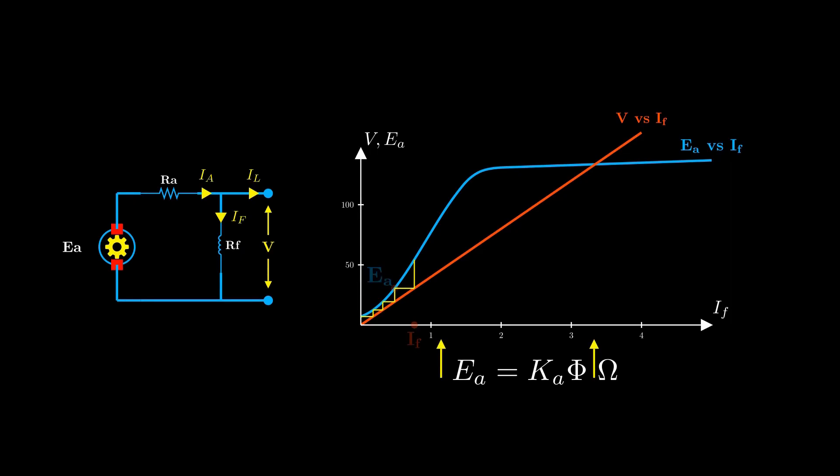At this point, increasing the field current no longer significantly increases the flux. The generator settles at a stable terminal voltage, determined by the intersection of the magnetization curve and the field resistance line.